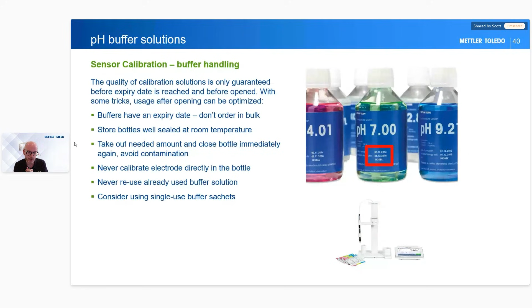You've got to be really careful about which ones you select. At Mettler Toledo, we offer a technical buffer. That has a calibration, and it has a verification certificate to say this is the pH we've tested it at, which is fine. You may be in an accredited laboratory where you need to take account of accredited buffers. So we do a range of DAkkS certified buffers. They are independently tested by a separate laboratory and come with the ISO 17025 accreditation laboratory confirming its certification.